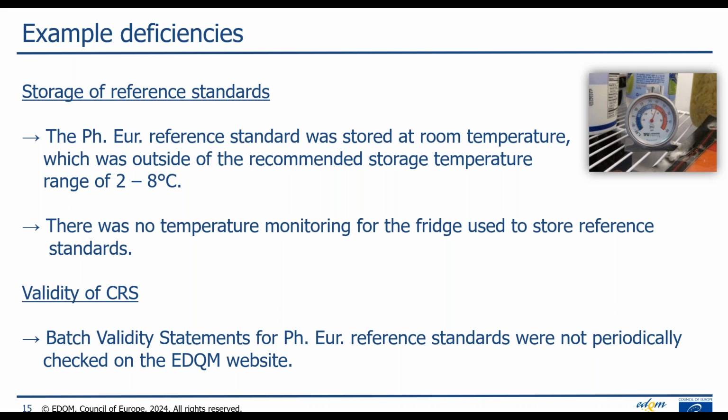Then in terms of storage of reference standards, as I mentioned, we would check whether they're stored in accordance with the instructions for use. So in a lot of cases, we find that in fact, the primary reference standards are not being stored in the fridge, but they're being stored at room temperature.